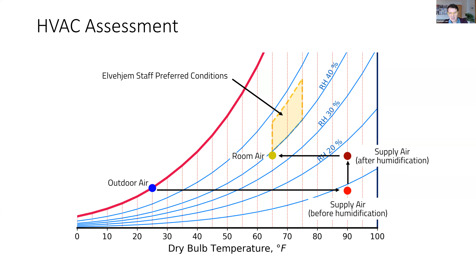That's what they want. Unfortunately, the actual system—if you follow these lines on the chart—takes the cold air in, a winter condition, heats it up, even adds humidity, and then it gets into the room, but it's just barely on the corner here. So this is not good—the HVAC is not performing well. Our scope is only supposed to be fixing the exterior wall, so HVAC is tertiary, but it's obviously hugely influential, as you can see.